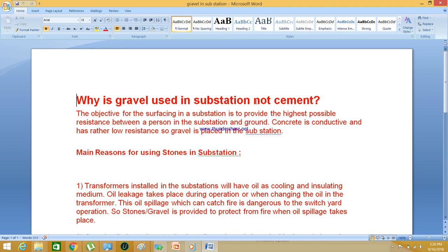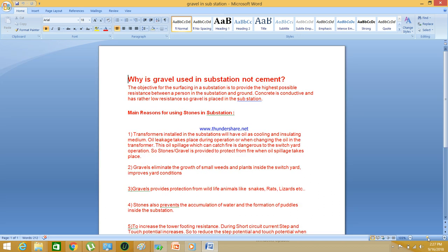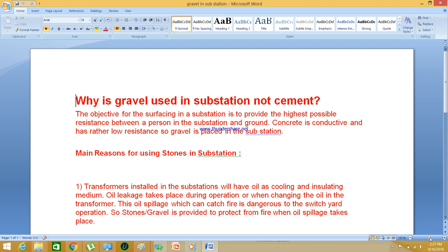Here you can see the object of surfacing. The object of placing gravel is to provide resistance from the ground. Whenever a person is standing in the substation, there has to be a resistance, and the resistance layer has to be good. Concrete is a conductive material and has low resistance, whereas gravel offers high resistance to the person who is operating in a substation. That's why gravel is placed in the substation — it offers high resistance compared to concrete material.